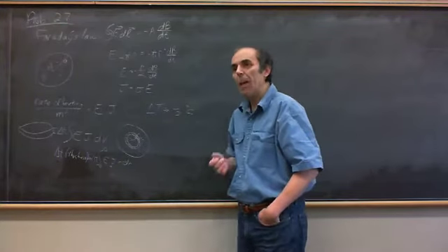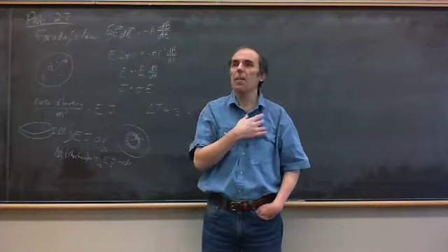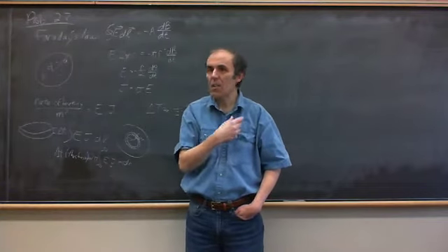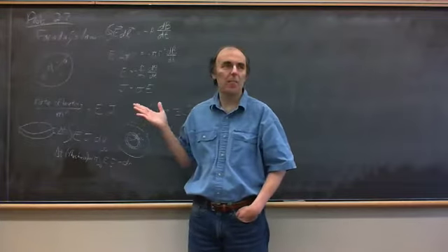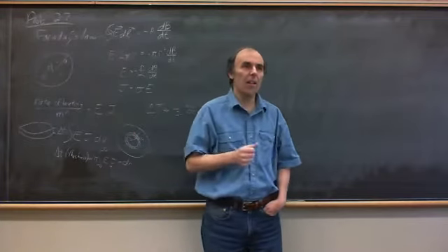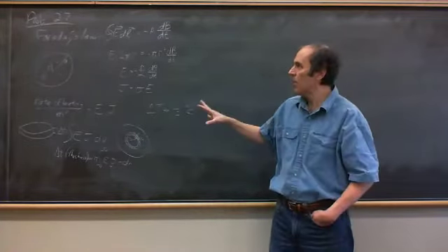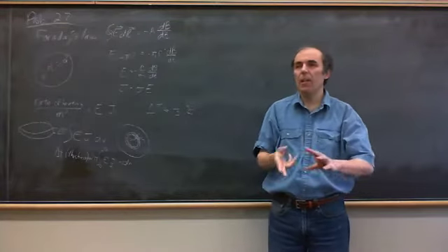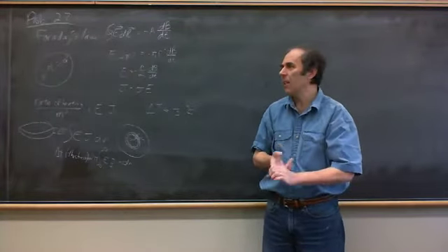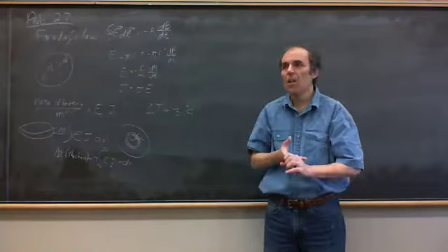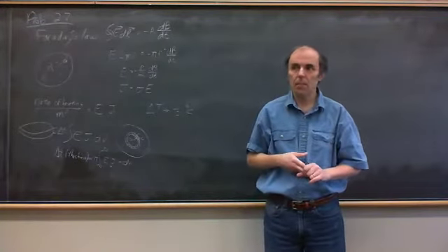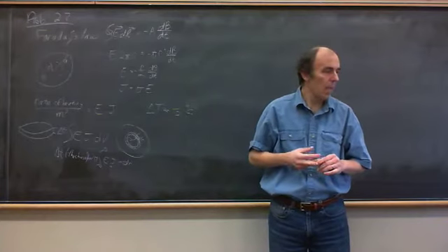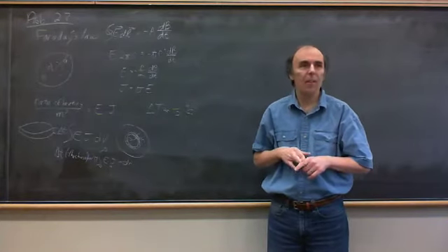If you happen to have a pacemaker and you did this, you might get currents induced in your pacemaker. So you have to be careful when a body has some high conductivity metal in it. Be careful with magnetic stimulation. You have to be careful with magnetic resonance imaging. Anything that has changing magnetic fields could cause this sort of heating or disrupt the system. That is problem 27.